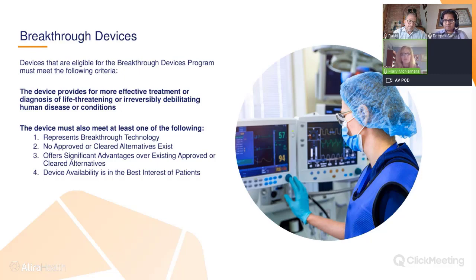So what are the benefits for a medical device manufacturer of getting a breakthrough device designation? It offers an expedited opportunity to interact with FDA experts through several program options to efficiently address topics as they arise during the pre-market review phase. It'll also help manufacturers receive feedback from FDA and identify areas of concern and agreement in a timely manner. Manufacturers can also expect prioritized review of their submissions, whether that be 510K, de novo, or PMA.